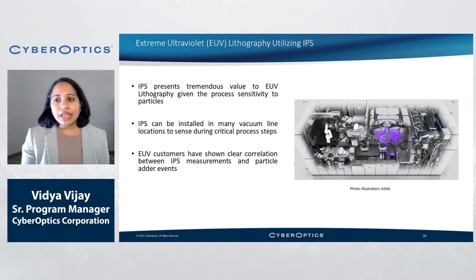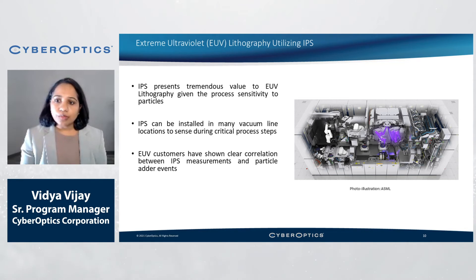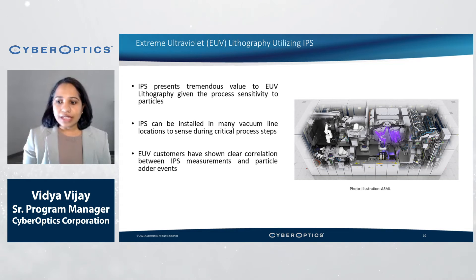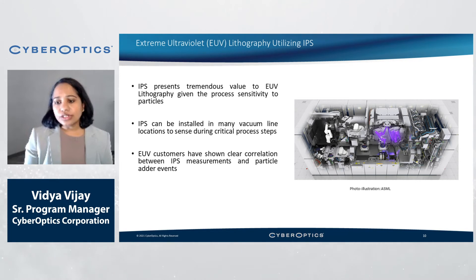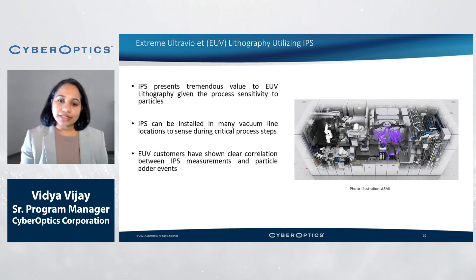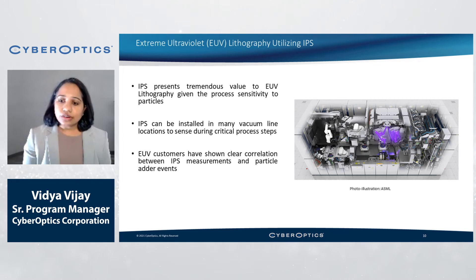We have seen many advantages of using the inline particle sensor to locate and troubleshoot airborne particles across photolithography environments. By recording sensed particles with time, particle-generating events can be correlated with events taking place inside the tool. CyberSpectrum software displays particle events in a graph with time, and can also store the data in CSV and other file formats. The IPS is normally used to troubleshoot particle problems in vacuum or gas systems, and EUV customers have shown clear correlation between IPS measurements and particle adder events.